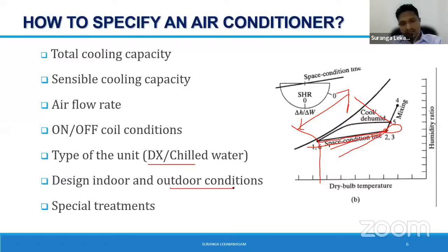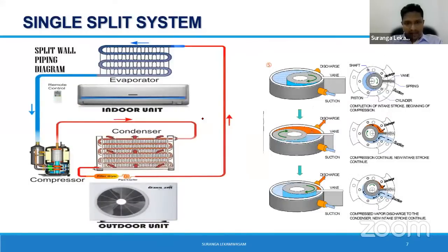Then the outdoor condition. In Sri Lanka, maybe 35 would be fine, but if you are putting it in the Middle East, 45 will probably be the condition. Then special treatments. If you install your outdoor unit in a very corrosive environment, closer to the sea, the fins may need special treatment, right? If you rely on air cooled condensers, probably your PCB needs to be treated with lamination or some kind of treatment. So all these need to be looked at, right? So with that basic understanding, I'll move to the different types of systems.